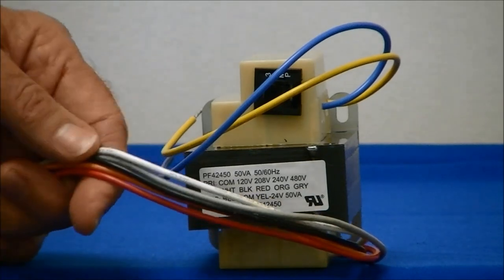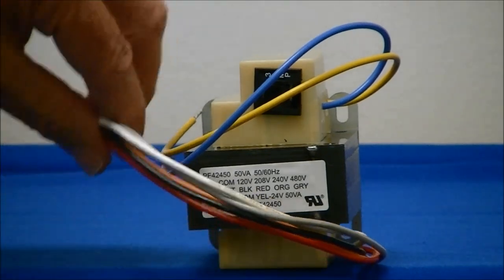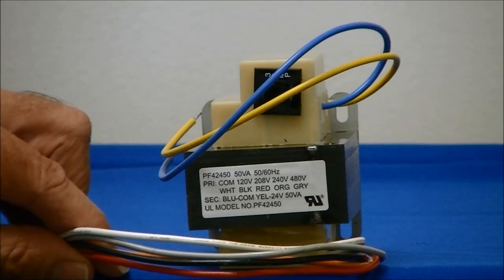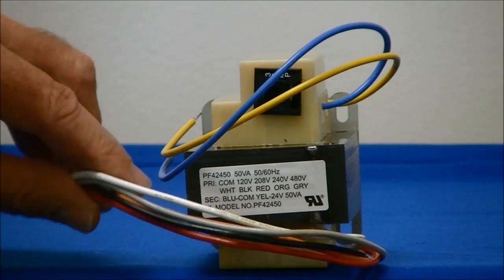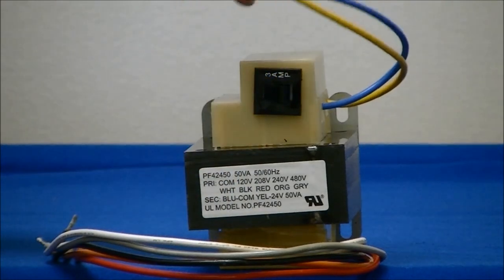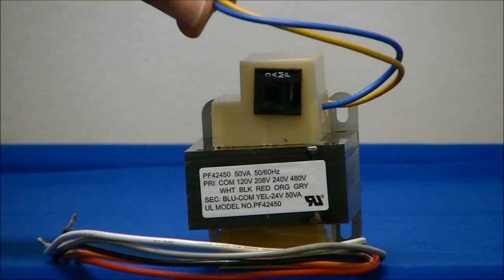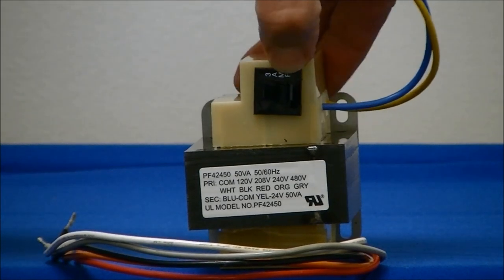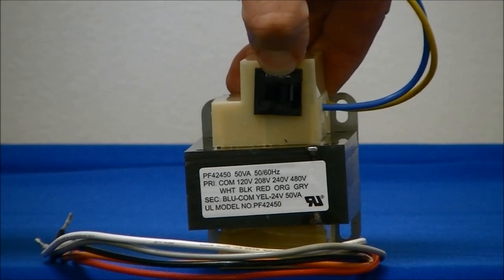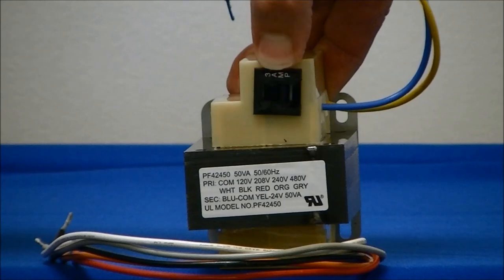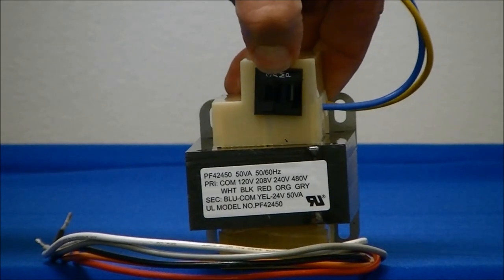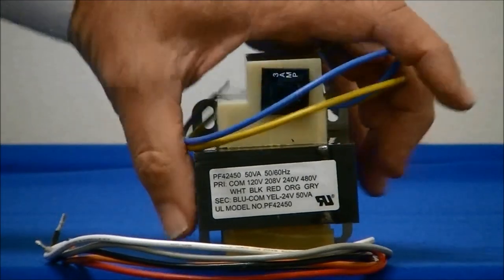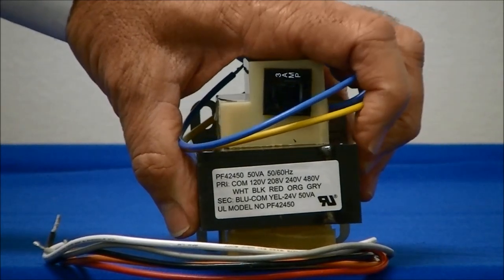Again, this particular transformer gives us multiple primary voltages. The primary voltage is the source of power that we apply to this, but it gives us a single secondary voltage, 24 volts. This transformer also has a protector so that if the load exceeds the rating of this, it will automatically trip and protect the transformer from burning up.